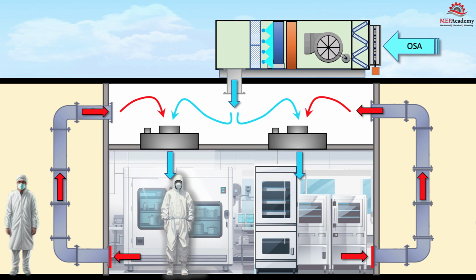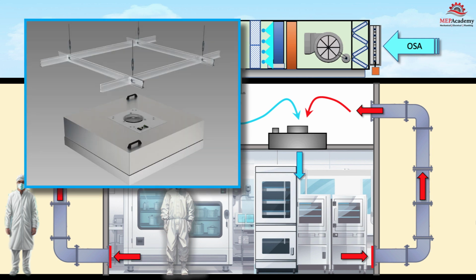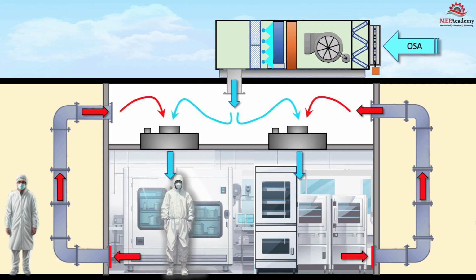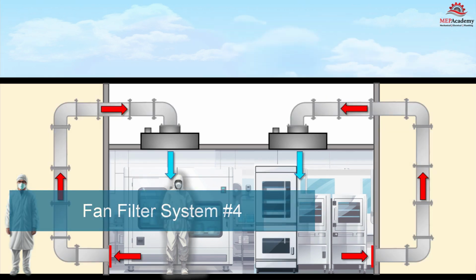FFUs are often used in conjunction with a ceiling grid system or other mounting methods to create a grid of clean air within a clean room. Multiple FFUs can be installed in a modular fashion to cover the entire ceiling area, providing consistent air cleanliness throughout the space. Fan filter unit system number 4.